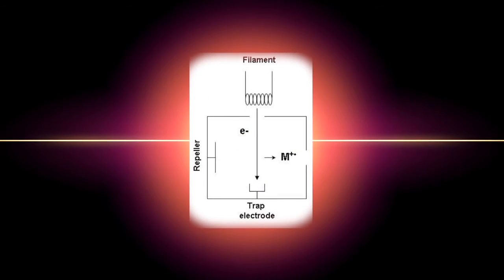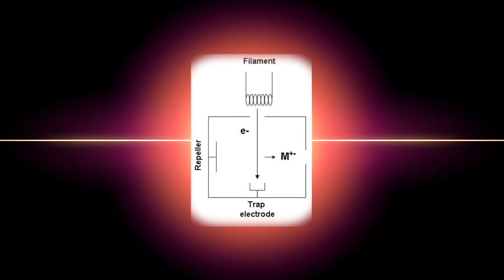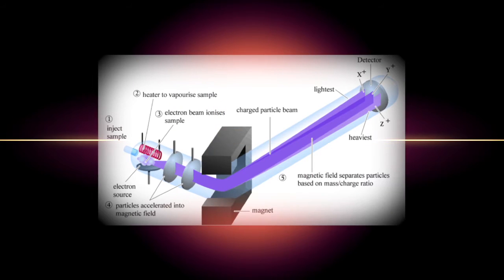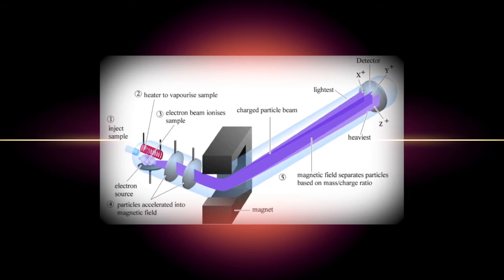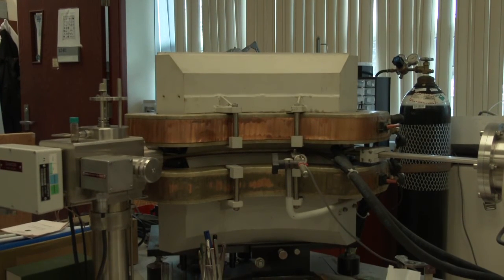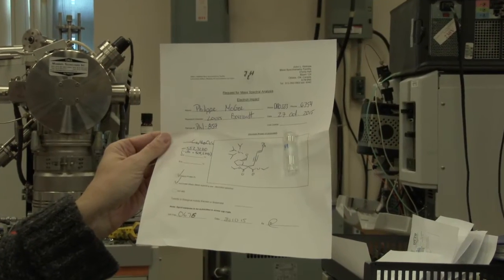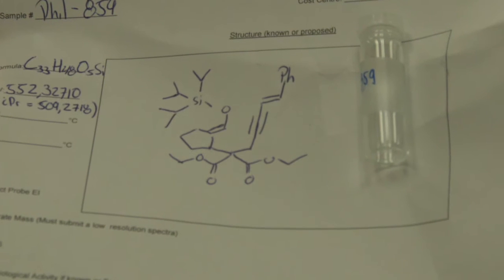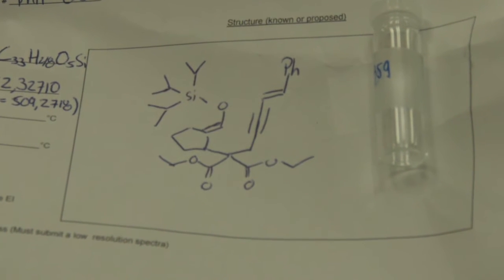So, how does it work? The source of an electron impact instrument contains a filament. Electrons created at the filament are accelerated to 70 eV, and they bombard the gaseous sample created in the source by the heater. The electron beam knocks out and ionizes an electron from the sample, creating a radical cation. The ionized ions can then be accelerated into the mass filter, the magnet, for further analysis. This form has been filled out correctly and also shows a possible mass for a likely fragmentation product.